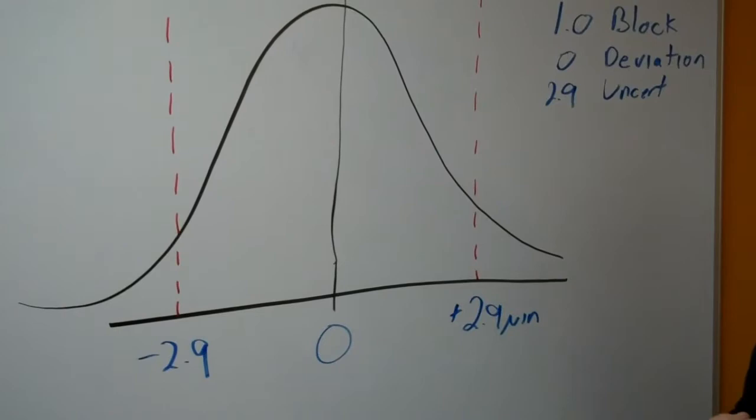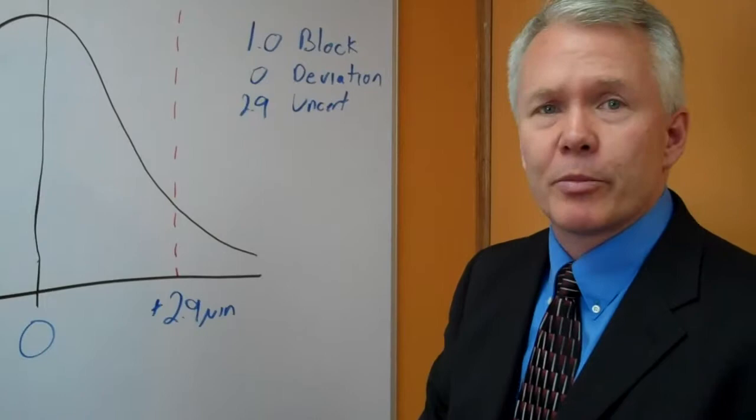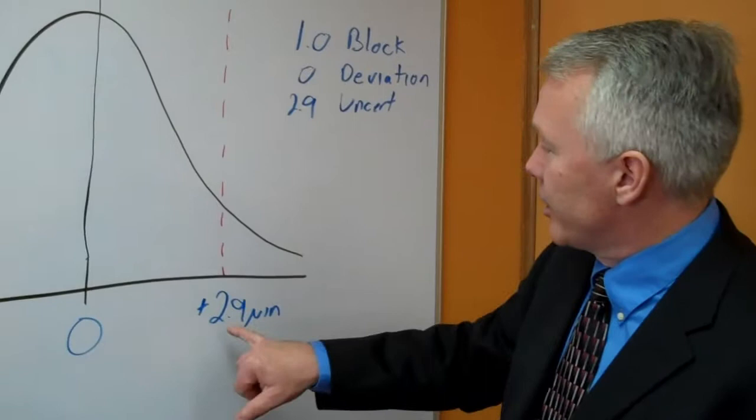We're saying it's kind of a standard deviation calculation built into the formula, and we look at the standard deviation of our whole process, which takes a lot of things into error, such as temperature, operator, machine, repeatability, stability, to determine how we get this 2.9 in the first place.